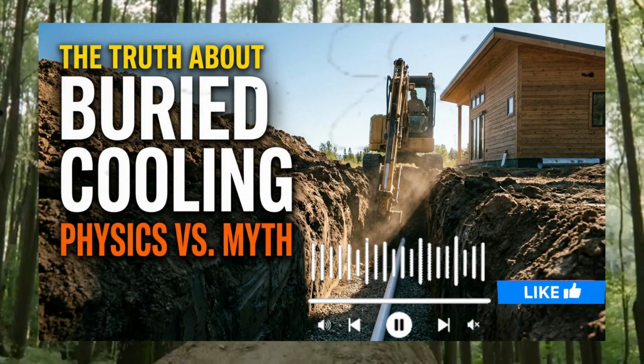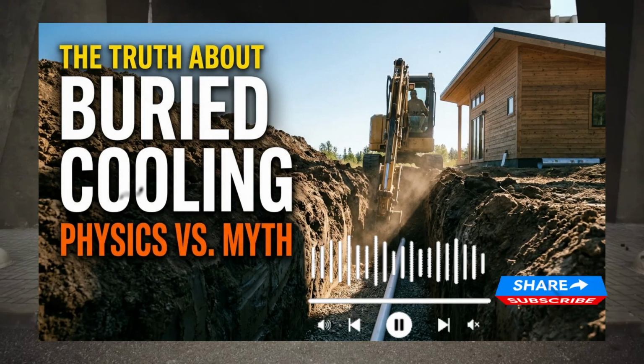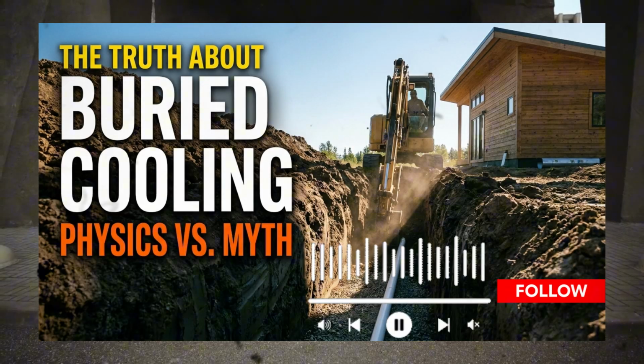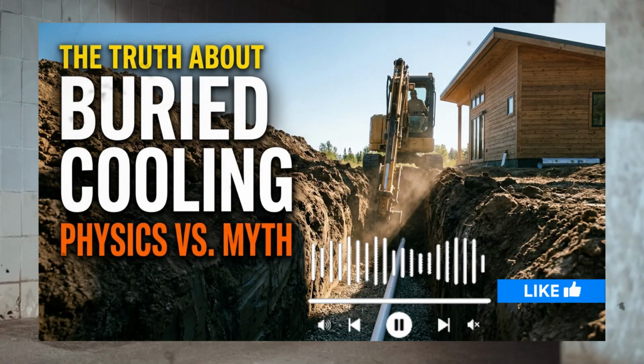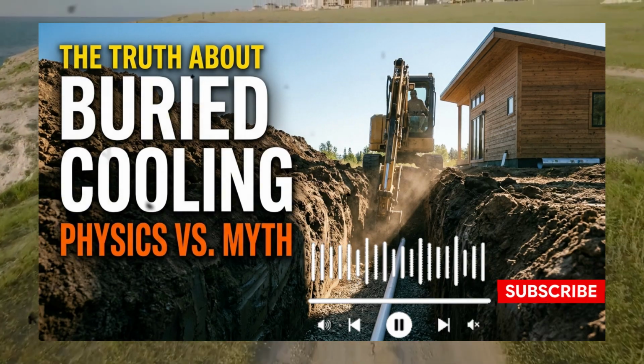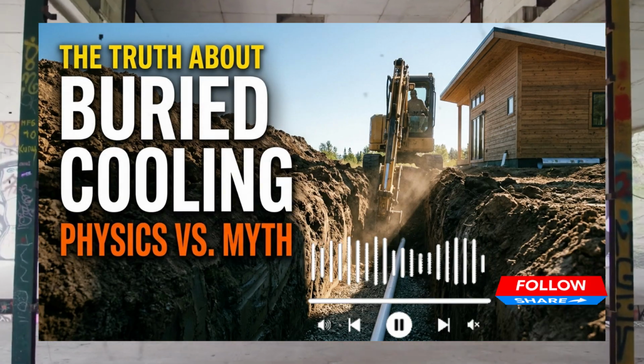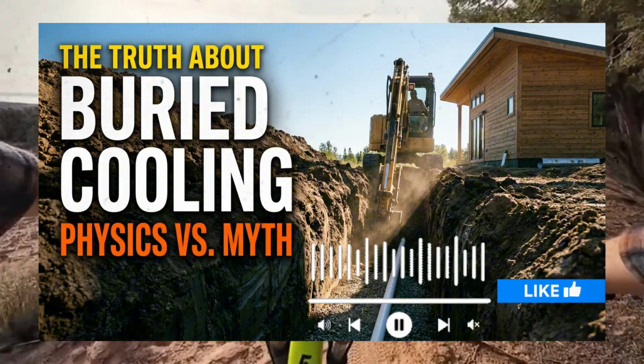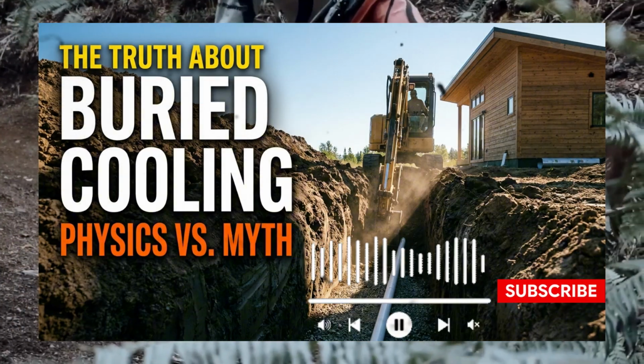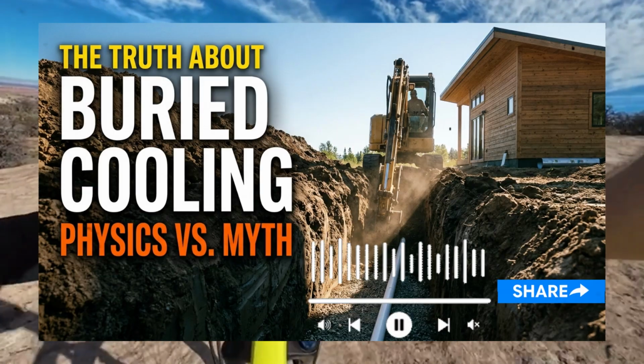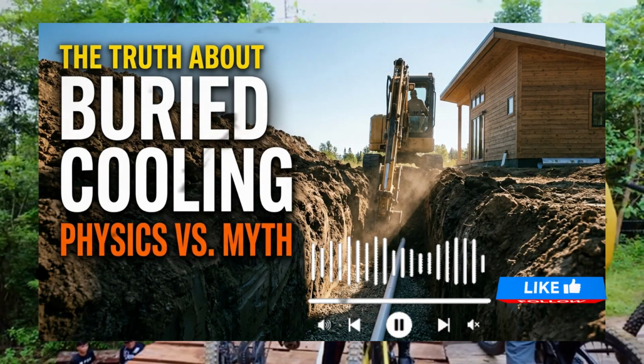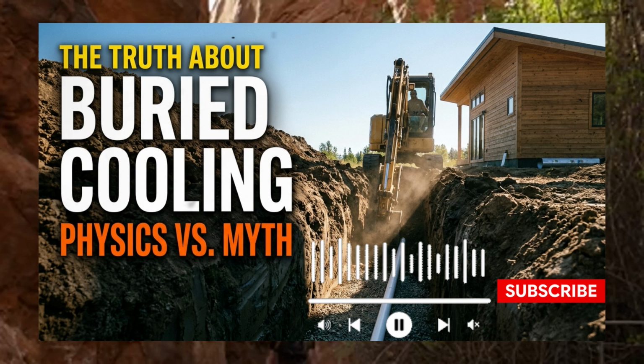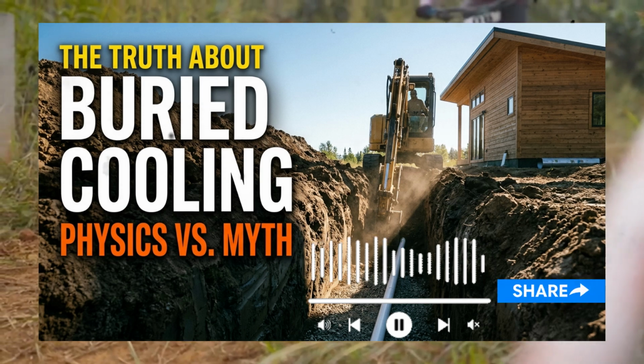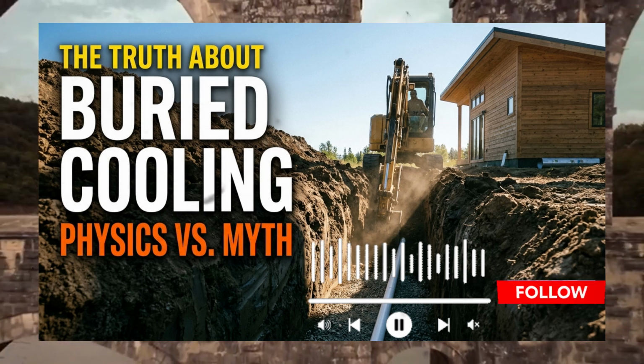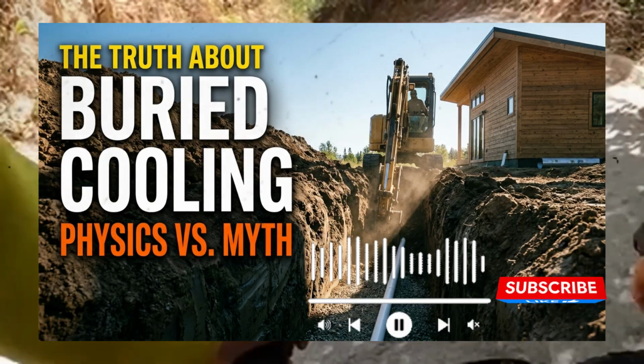If you plan to run an earth tube for winter preheating in cold climates, the system must be completely cleared of all summer condensation before the first hard freeze, and the condensation sump must be positioned well below the local frost line to prevent catastrophic freezing. The dual-season trial proved that our system was a highly effective engineering tool, but it also humbled us. It showed us that we cannot outsmart the laws of thermodynamics with simple shortcuts. Nature will always find the weak point in your design.